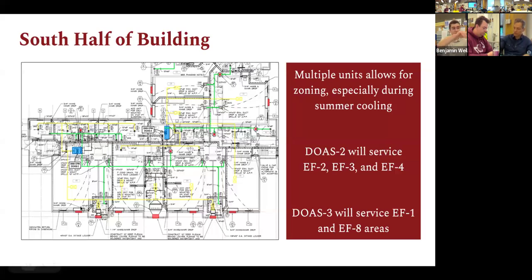Again, in red, that's where all of the unit ventilators we propose to seal off. That would just look like pulling off the louver, putting in a piece of foam board, sheet metal, and then air sealing around, putting the louver back. And then again, new supply and return ductwork. And it's not pictured in this drawing, but again, the hydronic system really doesn't get touched at all. We can use all of that existing piping that runs the unit ventilators, especially because even the chilled water, which is above dew point, it means that we don't have to install any sort of condensate system. So that's not serving any latent cooling loads. You're able to just use all that piping with no condensate issues.